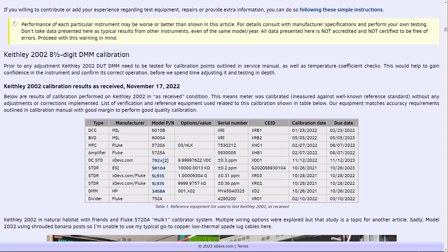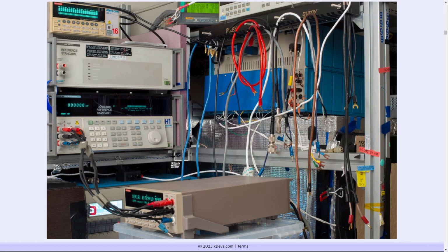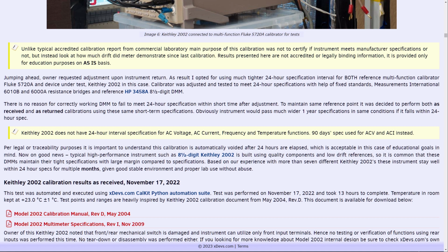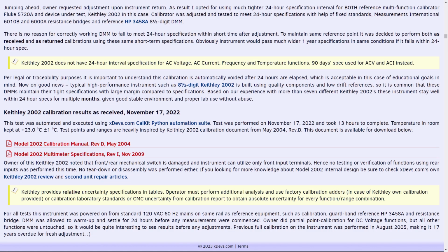The photo below shows the measurement setup as it was tested, and the ambient temperature in the lab was kept at 23 degrees centigrade within a couple of degrees. The Model 2002 multimeter was allowed to warm up for at least a day, and all the tests started in the middle of November. Calibration procedures were inspired by the Model 2002 calibration manual, revision D, May 2004, and the specification manual, revision I, November 2009. All tests were automated as much as possible to reduce the risk of human errors and save time. All points are verified against 24-hour specifications and not typical 1-year interval specifications. AC voltage and AC current functions were tested against 90-day specs, since no 24-hour interval is available from Keithley for the Model 2002.